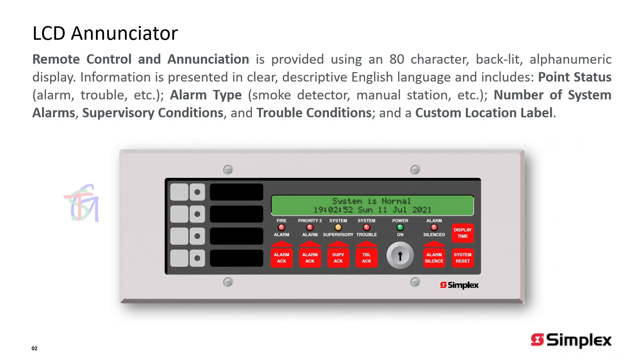The remote control and annunciation is provided using an 80-character, backlit, alphanumeric display. Information is presented in clear, descriptive English language and includes point status, alarm type, and a custom location label, number of system alarms, supervisory conditions, and trouble conditions.